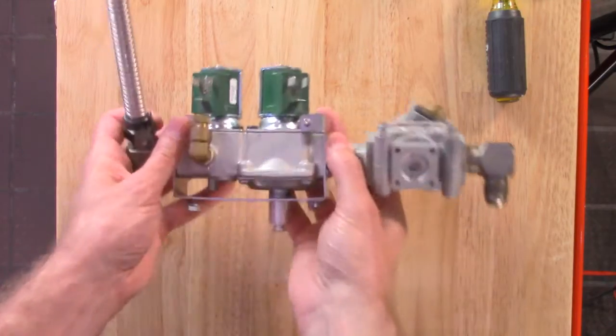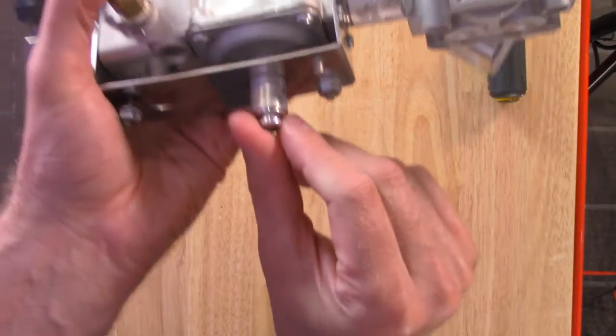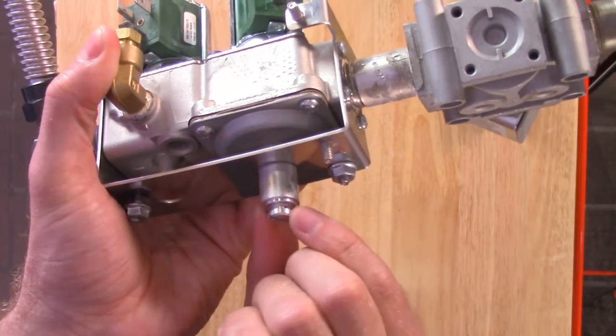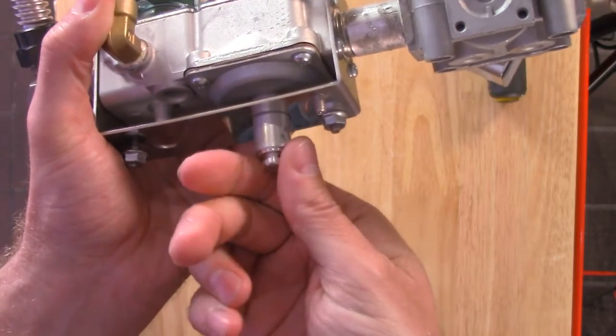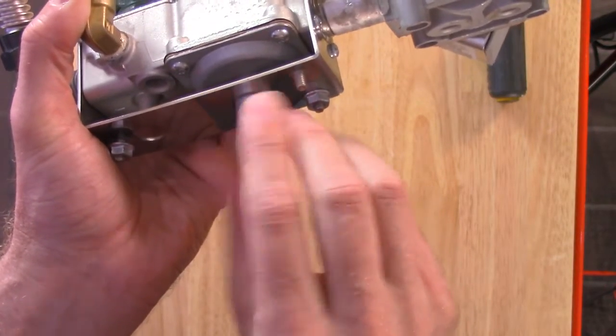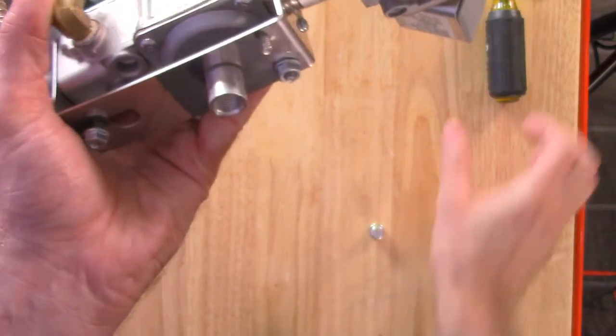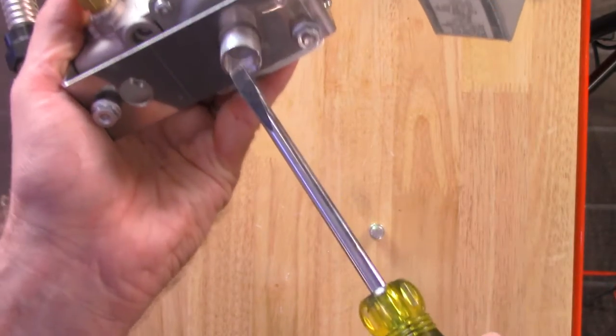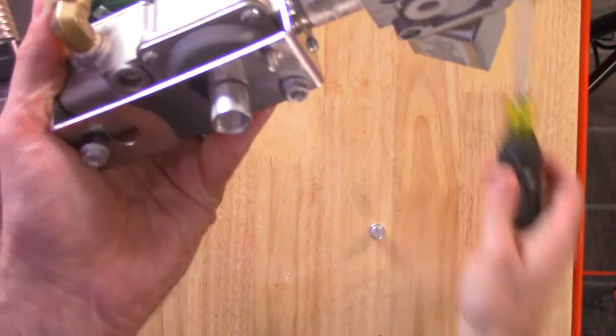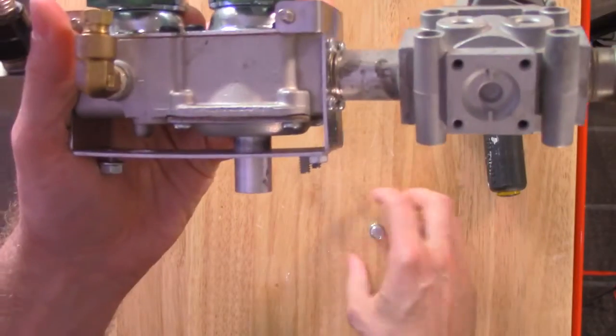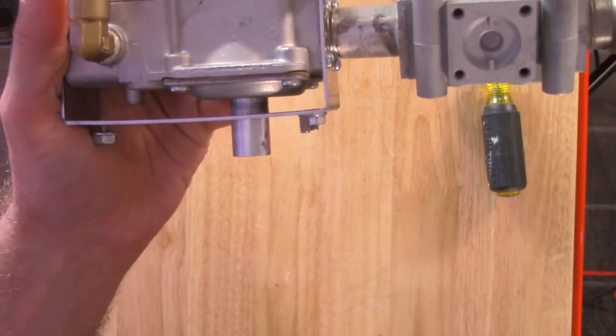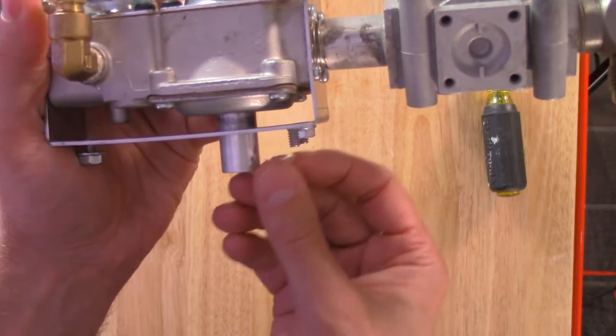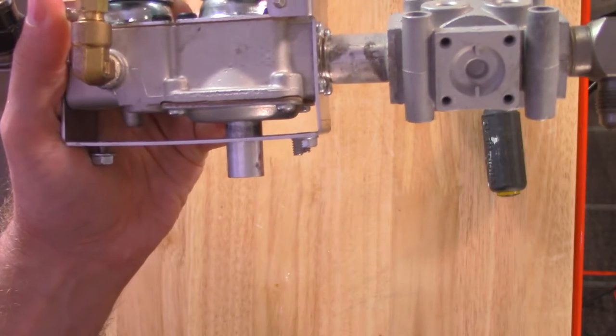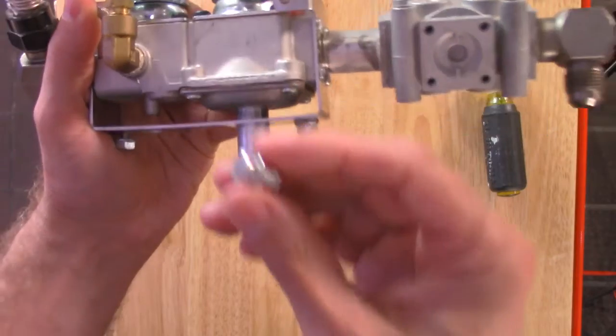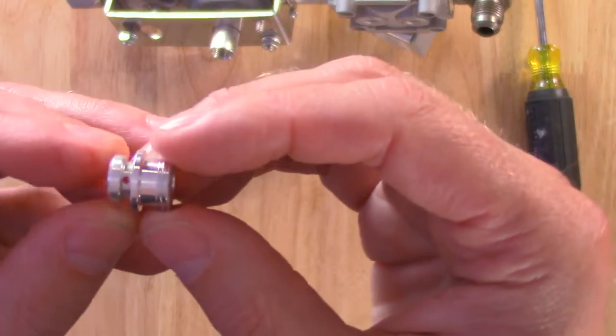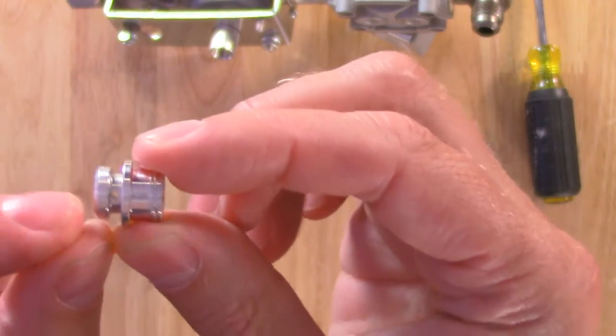So the atmospheric equalization hole is this right here, and you can see the hole right there. Actually, if you were to remove this, this is where you can gain access to get inside here, and you could go ahead and adjust your gas pressure. Now, when you're at the location, if they remove this cap, or the atmospheric equalization hole, and all of a sudden it starts heating up and the burner comes on, it's pretty safe to say that the atmospheric equalization hole right here has gotten clogged.